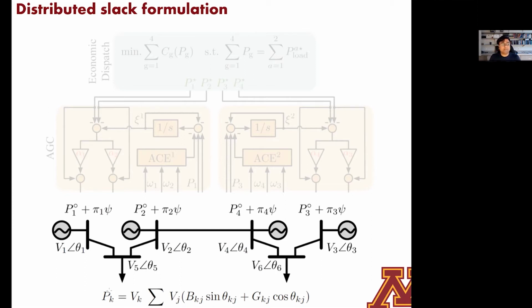But just remember that in the plain vanilla version of the power flow problem, you are forced to leave one generator as the slack bus that's going to pick up all the losses, any load that you haven't accounted for. And just remember that the power flow problem at the end of the day is attempting to reflect all that's happening from an operations point of view across a time horizon going up to a few minutes and across large spatial distances, capturing generators and loads in these many different balancing areas as we pointed out.